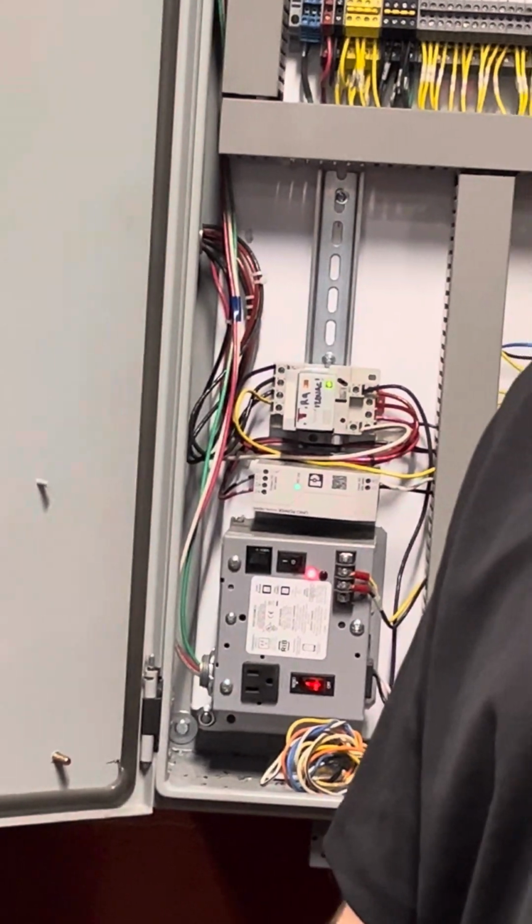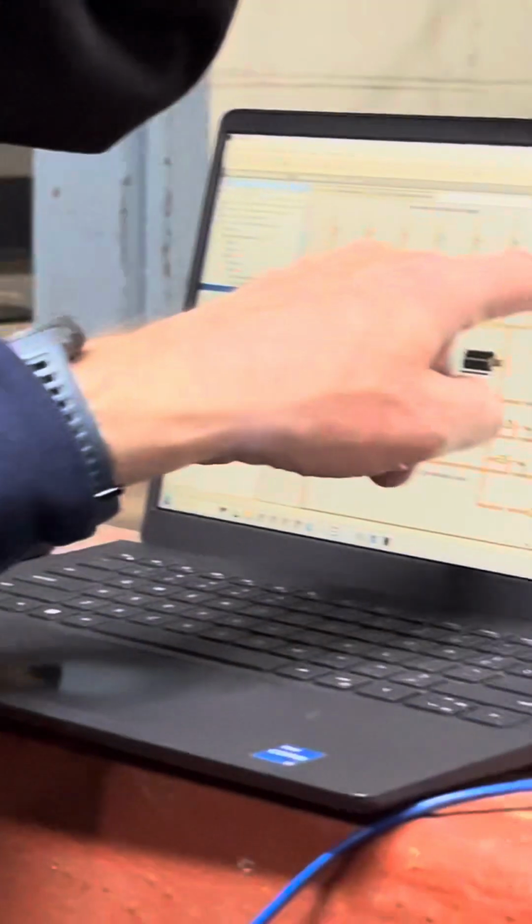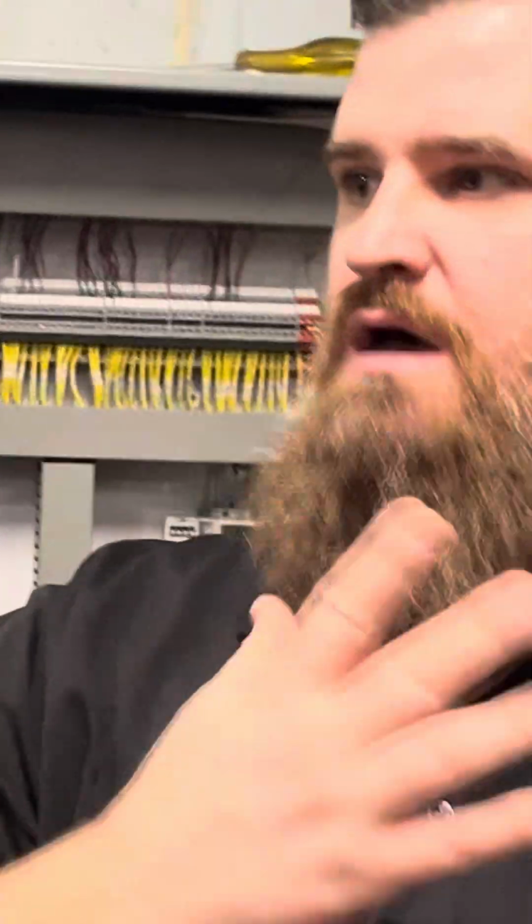Okay. Derek, did you see this? So there's an override here for the fan to turn on and off. Yeah, so you guys can override the fan on and off, but if you've lost this, you have no control of any of this. So you got to jump it, go disconnect the damper actuators, open those, pin them open, do whatever you got to do to make sure that you've got at least some way to pull air into this room.